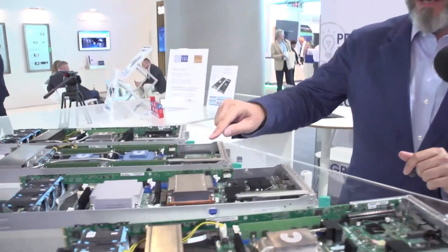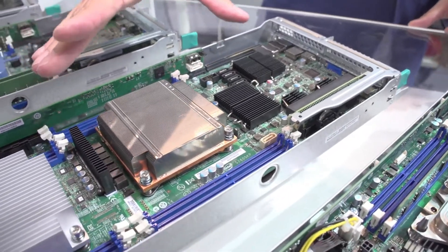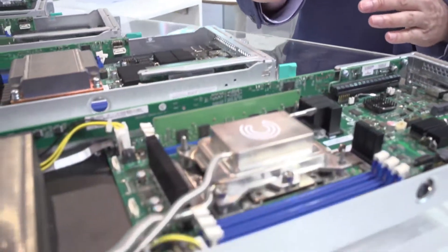We provide cooling solutions without water that can handle really high-power CPUs coming next generation. We've been reading about new Skylakes and processors that are over 200 watts — how do you take that heat away? It's a very important moment right now because the market is providing customers with high-TDP CPUs above 200 watts. At that level, the classical solution with a heatsink and fresh air blown through cannot cool CPUs above around 165 to 200 watts.